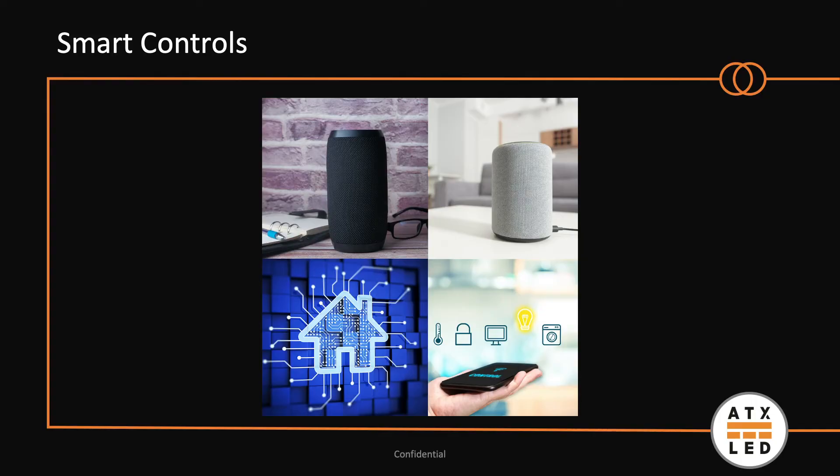So obviously there's a lot of control there. How are you controlling the lights — the dimming, the color tuning? For our system, as you mentioned, it's an end-to-end system. We took the approach of starting with a blank sheet of paper and designing lighting from scratch. What we came up with was an end-to-end DC low voltage solution — from the beginning of the distribution out to low voltage switches, and then out to the LEDs, all low voltage DC. The controls can be done either from local switches, through apps, or through third-party integrations with really any of the control system brands, either on demand or through scheduling and more advanced features.